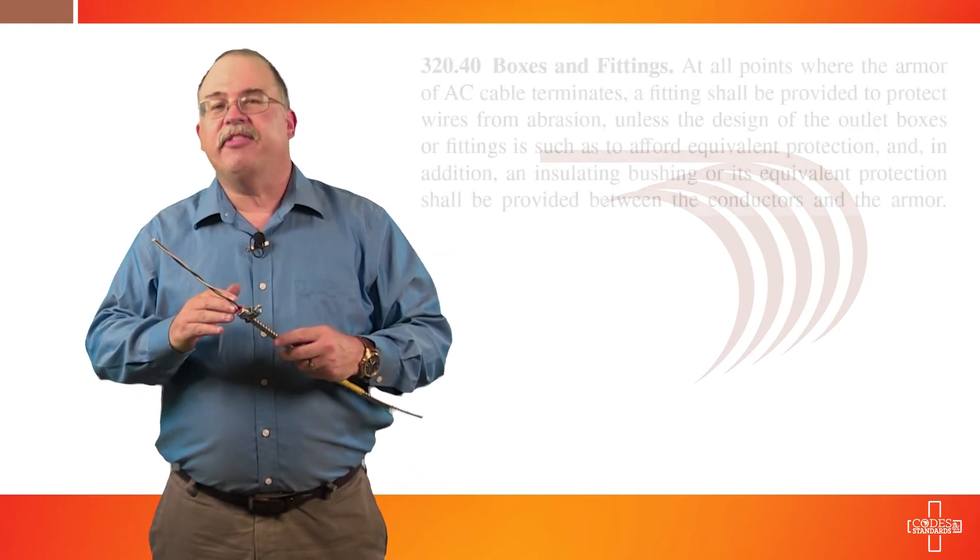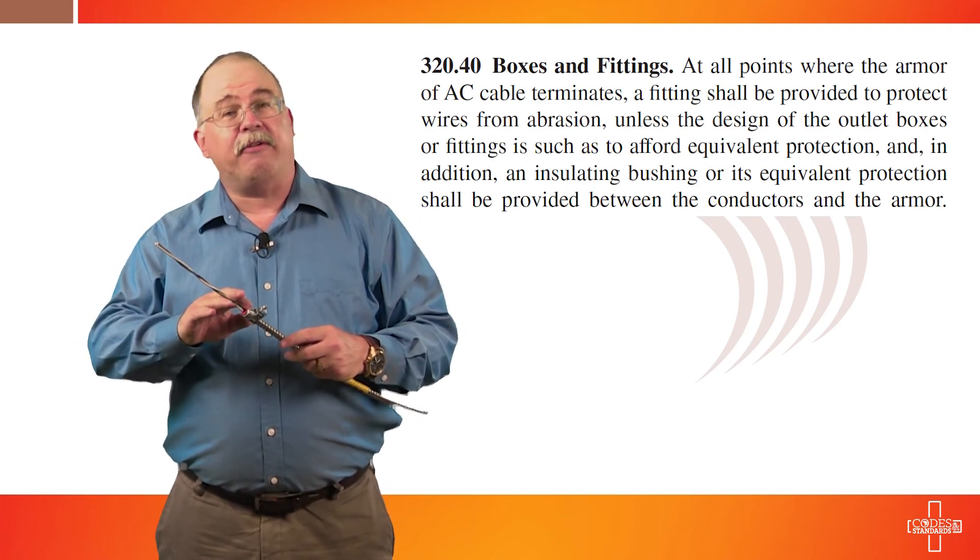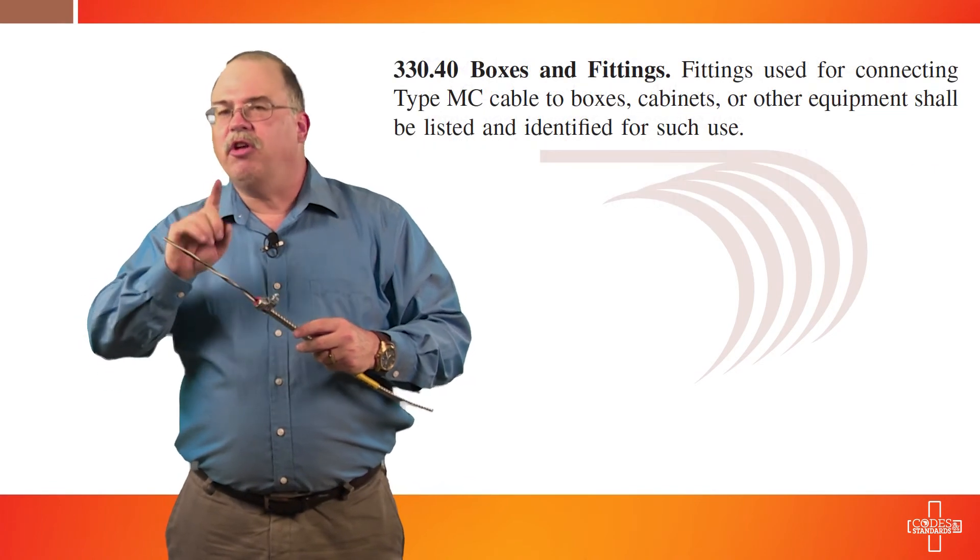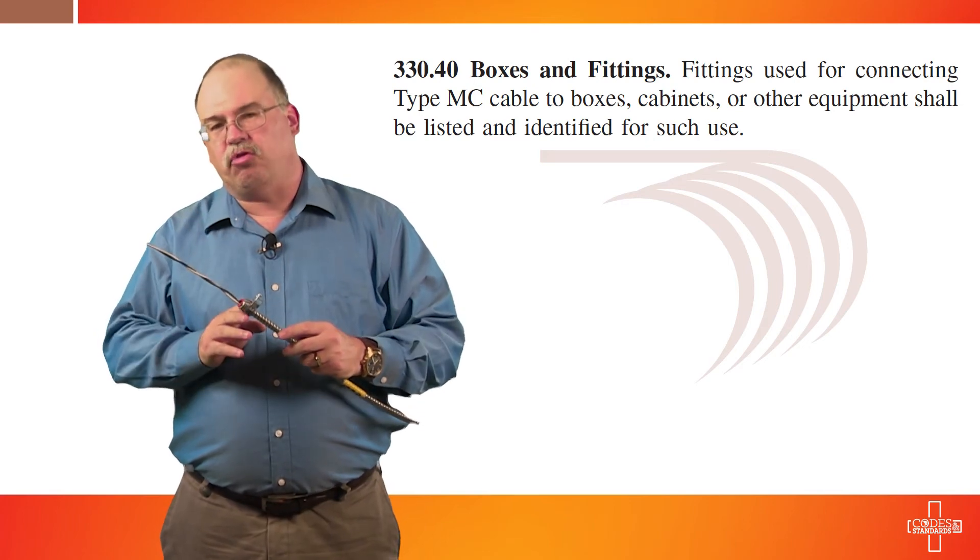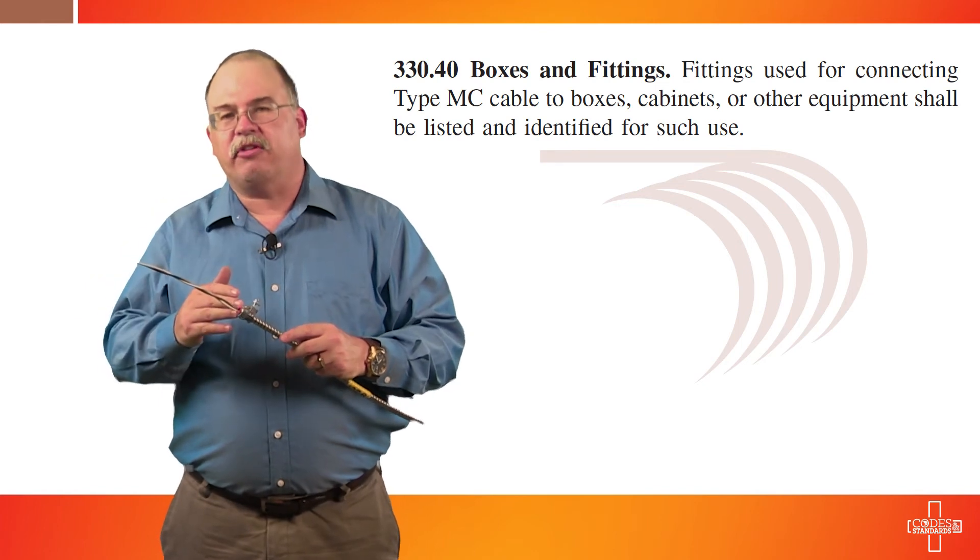Now there's a couple interesting things to talk about when it comes to fittings. You'll notice in this fitting it has an anti-short bushing in the end. Type MC products do not require an anti-short bushing. If I was dealing with a Type AC or armored cable product, then I would need an anti-short bushing in accordance with section 320.40 of the National Electrical Code. But since this is a Type MC product, we would look at section 330.40 of the National Electrical Code which deals with fittings and connectors. And you'll notice that it doesn't require any anti-short bushing. This product happens to have it integrated into the connector and that's perfectly fine.